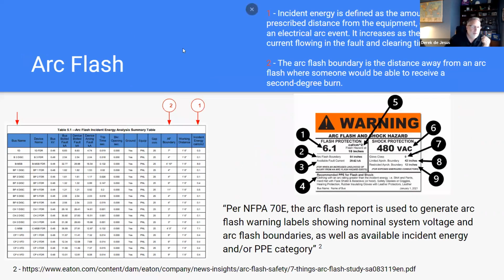I think if we look at this table here, this is a good table where you're going to start to get a lot of these incident energies really low, boundaries really low. So your PPE requirements are always going to be the same. When you're looking at distribution panels past like a 120 to 480 volt panel board, they're really not going to change any differently. But that's just the minimum standard that we've applied. It's usually for the higher incident energy spaces where you're going to have a different cal rating. A lot of owners and their maintenance team, it comes down to the operations team—what engineering protocols are they going to put in place for working within that space? Are they going to do a closed transition switch operation and maintenance? Probably not, right? So that incident energy can be reduced if they properly plan their work for maintenance.